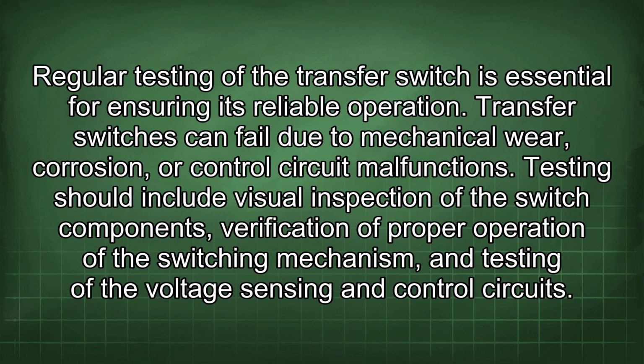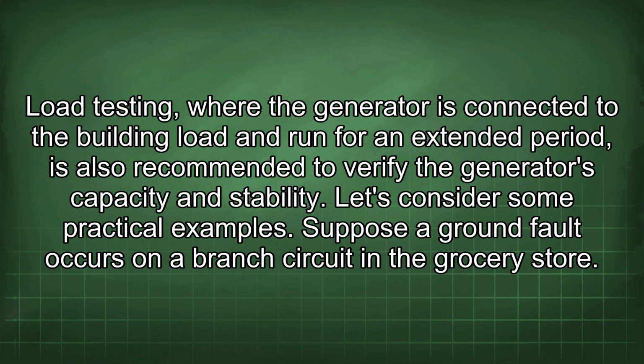Regular testing of the transfer switch is essential for ensuring its reliable operation. Transfer switches can fail due to mechanical wear, corrosion, or control circuit malfunctions. Testing should include visual inspection of the switch components, verification of proper operation of the switching mechanism, and testing of the voltage sensing and control circuits. Load testing, where the generator is connected to the building load and run for an extended period, is also recommended to verify the generator's capacity and stability.